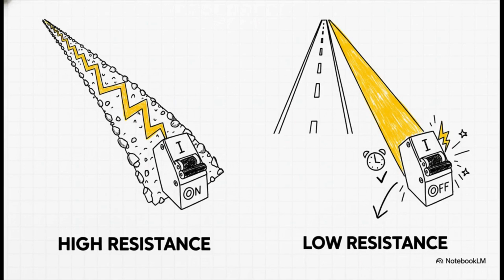But you know what? It doesn't matter if it's a rod, a tape, or the building's foundation. The goal is always the same: to create a path with the lowest possible electrical resistance. A low-resistance path is what guarantees that during a fault, the current will be massive enough to operate those protective devices instantly and reliably, every single time.